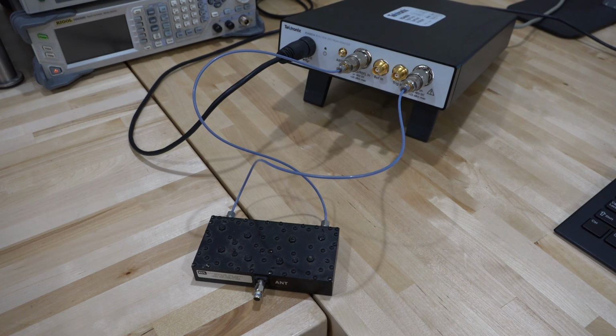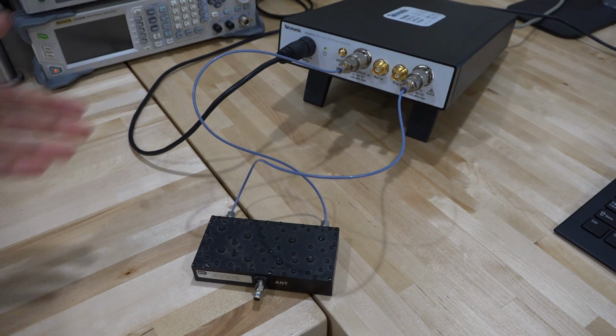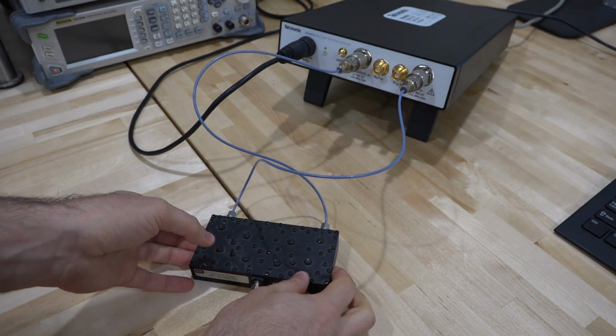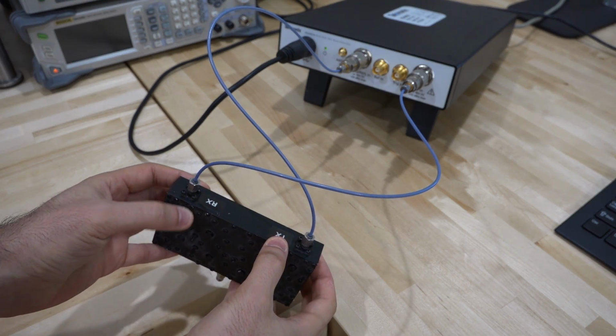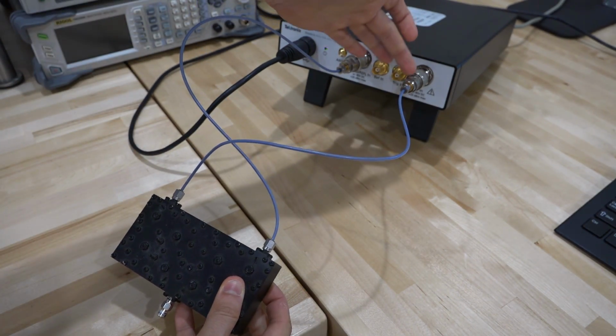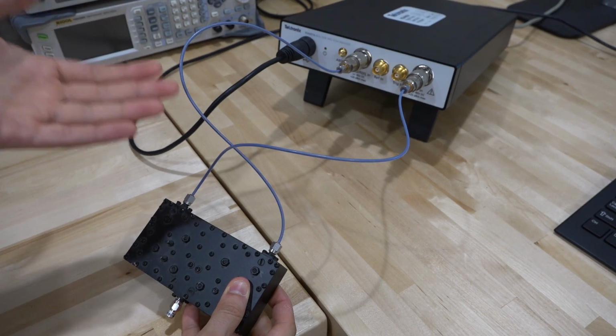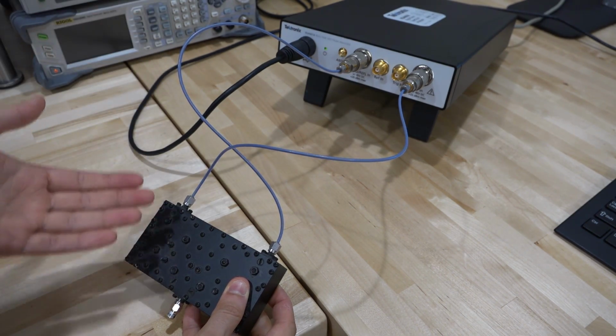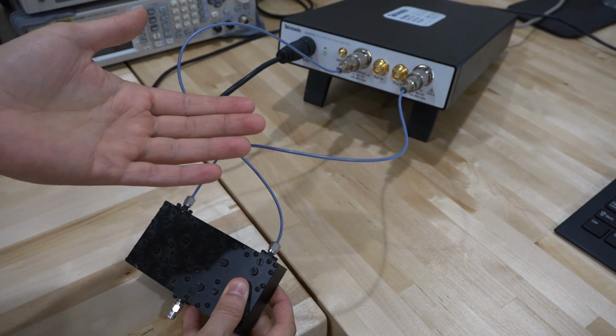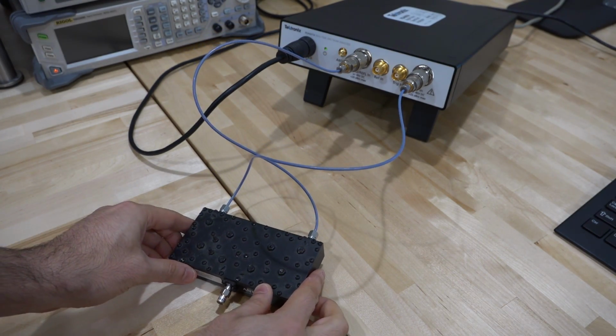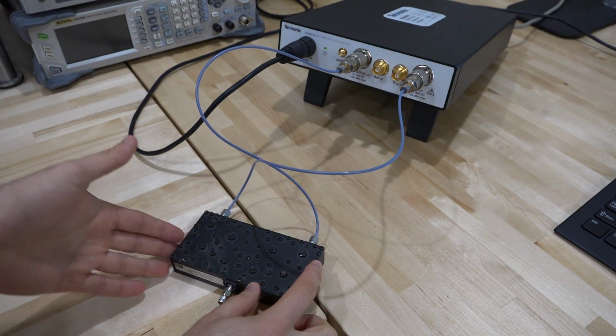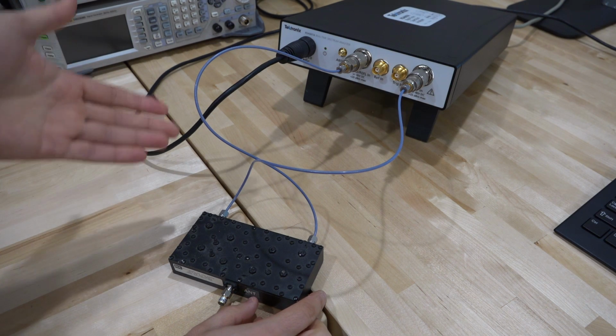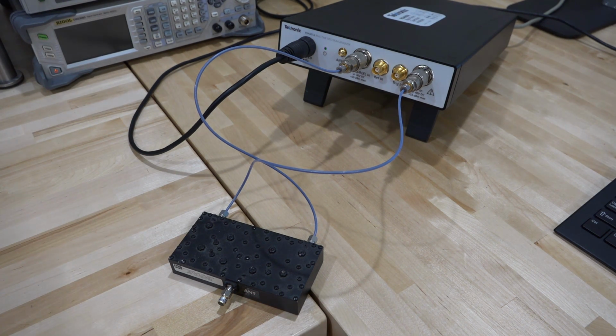And finally, the TX-RX isolation can be measured by connecting the tracking generator directly to the TX port and taking the RX port and connecting it to the receiver. And this is a really important parameter because you want to make sure that the transmitter doesn't leak into the receiver. Now, normally you want to do this with an exceptionally high dynamic range, but we're going to be limited here by the instrument. Nonetheless, we can see if there is any relationship between those two ports.